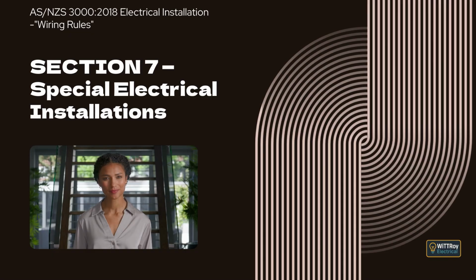Clause 7.2.10.4.2 Segregation of cables. This clause explains that conductors supplying MRL lifts must not be enclosed with conductors of different safety services or with conductors of any other wiring system, and that effective segregation may be achieved using divided enclosures, compliant wiring systems, or by ensuring conductors of different safety services are not combined within the same multi-core cable.